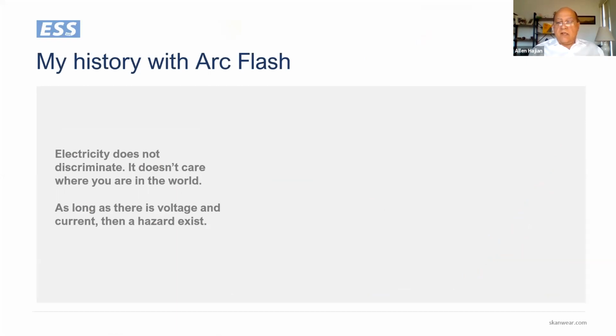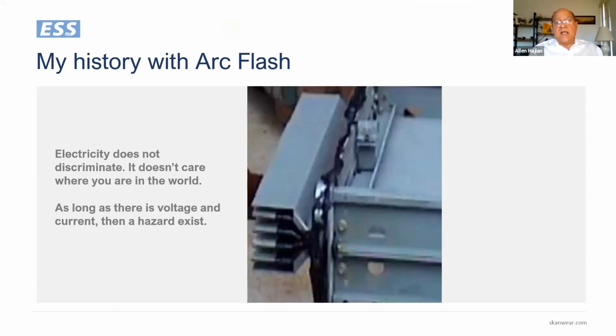So we watched the video about Mark, and I have a similar experience with one of our employees. This was the first week I was working with our service organization. Mark was doing the measurement on the phases, and the accident that our employee was involved in was actually a phase rotation measurement on a bus duct. As you can see in the picture, the phases are very close to each other, and there is potential for an arc flash using just the alligator clips.